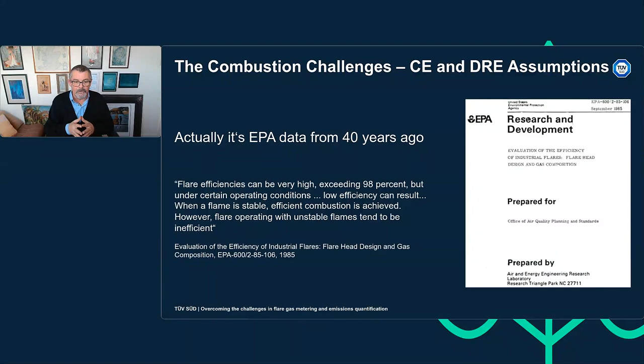Now, there are some realities for me about CE and DRE. The efficiency of a flare, we saw the image earlier with 2 flares, one efficient, one inefficient. Many factors affect the efficiency. The design of the flare tip, as I mentioned, is not just a piece of pipe, it's a highly engineered, sophisticated piece of metal designed for flare optimization. The exit velocities at the flare tip: it's expecting a certain velocity to be there to optimize combustion. It has an operating range like any other piece of engineering.